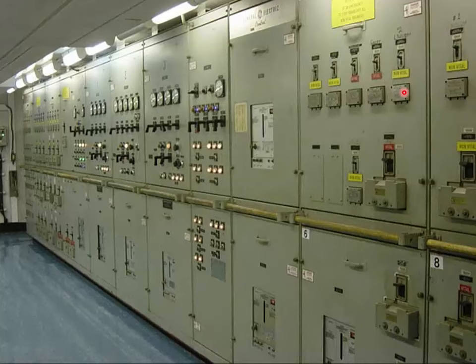In other words, a short circuit is where the power can go to ground, and it can be a very, very large current flow, which could cause a circuit breaker's contacts to weld. They can spot weld and not open when you have these extremes. In some cases, you can have as much as 100,000 amps in about a quarter of a cycle. So on our ship, and not all ships are like this, this is a fairly high quality system. You have a circuit breaker for normal overloads, and that would trip to a middle position. It can be manually reset. And then you have these fuses so that if you have an extreme current flow from a short circuit, the fuse will open and protect the circuit.